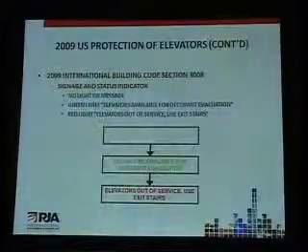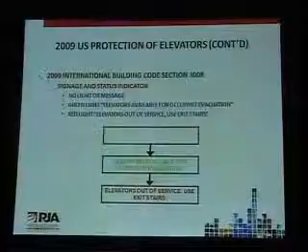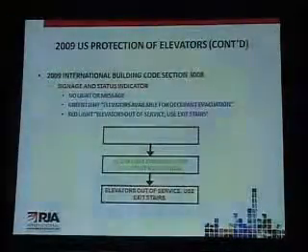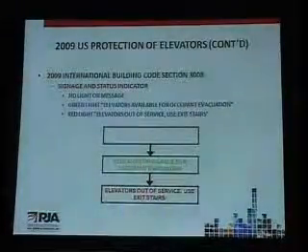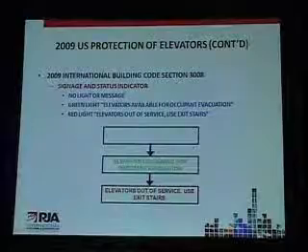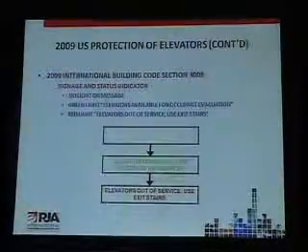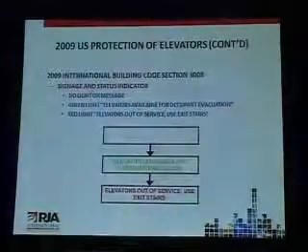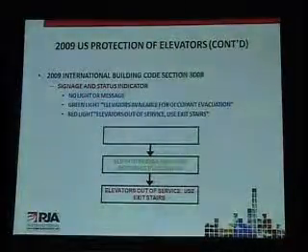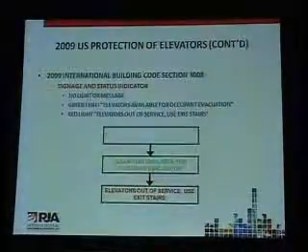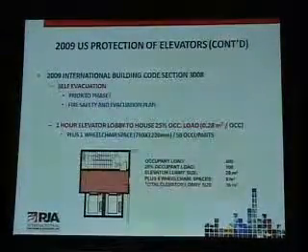One of the drivers for allowing a self-evacuation is this new dynamic signage. Jim had previously indicated that you'll have a sign in every elevator lobby that says you cannot use the elevators during a fire, you should go use the stairs. Well, now there is no sign at all in normal operations. If the fire alarm in the building goes off, the sign turns to a green sign that reads that elevators are available for occupant evacuation. If phase 1 emergency recall is initiated, then the sign turns red and says that elevators are out of service, use the exit stairs.